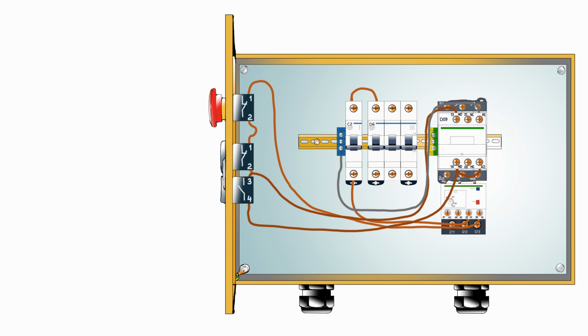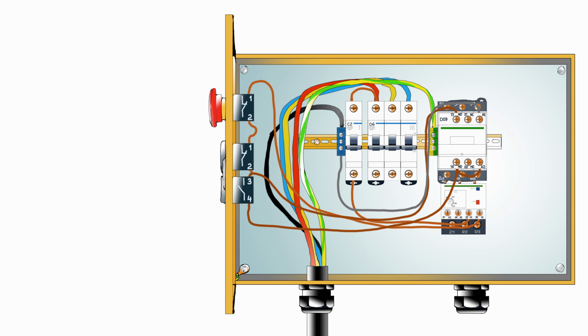And then on the power circuit side, it's pretty straightforward. All the power circuit components are connected in series with our electric motor, and it shouldn't be a difficult thing for this non-reversing direct online starter. So we just connect our supply to the top of our circuit breaker, and then from the bottom of our power circuit breaker we take our 3 conductors, and then we connect them to the top of our switching contactor.